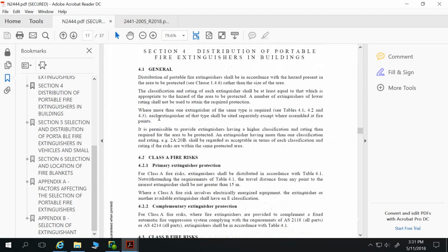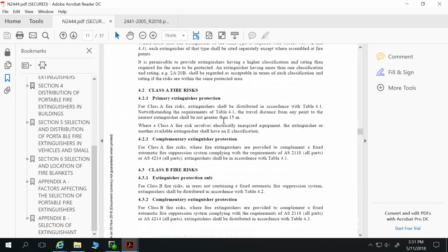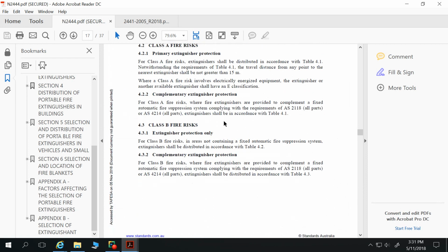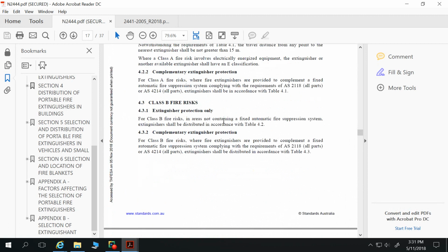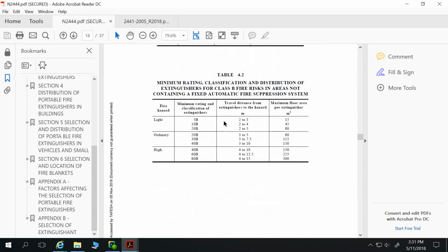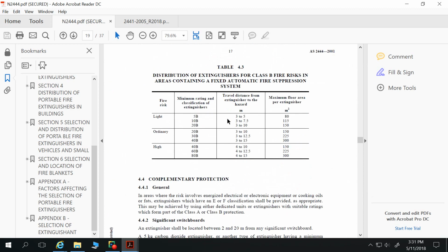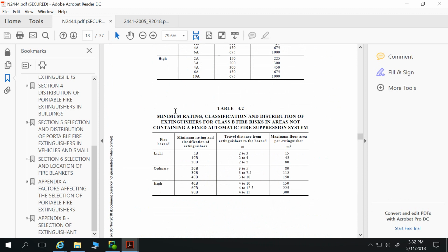And same sort of thing. So that's Class A fire risk. So that's general combustible stuff, woods, plastics, and whatnot. Class B fire risks, that's those flammable fuels and things like that. So tins of petrol and so on. And we've got a table here for Class B. So distribution of extinguishers for Class B fire risks in areas containing fixed automatic fire suppression and one without automatic fire suppression. So just be aware that there are those parameters around frequency and placement of them as well.